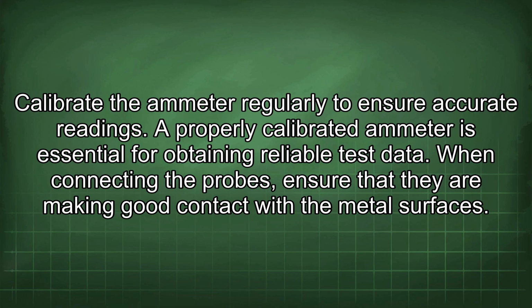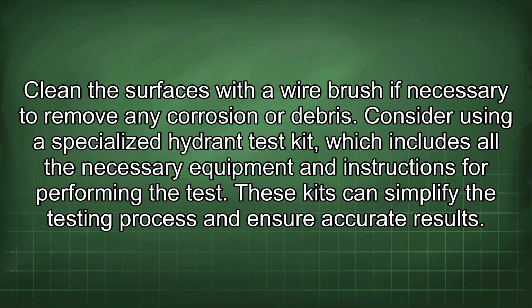When connecting the probes, ensure that they are making good contact with the metal surfaces. Clean the surfaces with a wire brush if necessary to remove any corrosion or debris. Consider using a specialized hydrant test kit, which includes all the necessary equipment and instructions for performing the test. These kits can simplify the testing process and ensure accurate results.